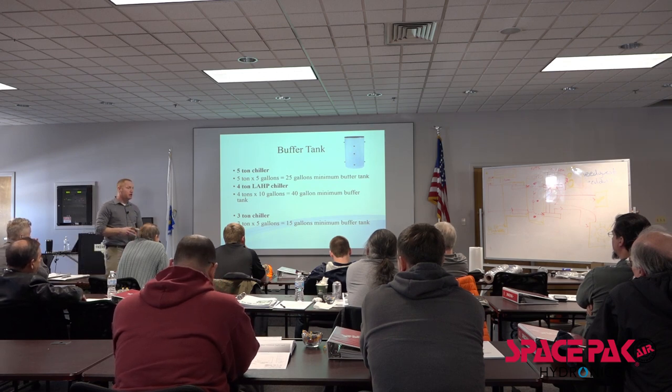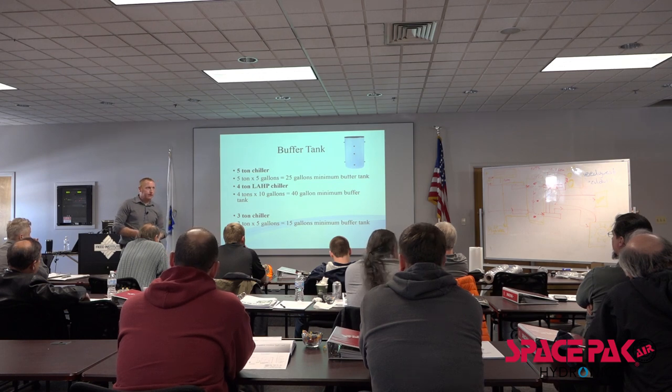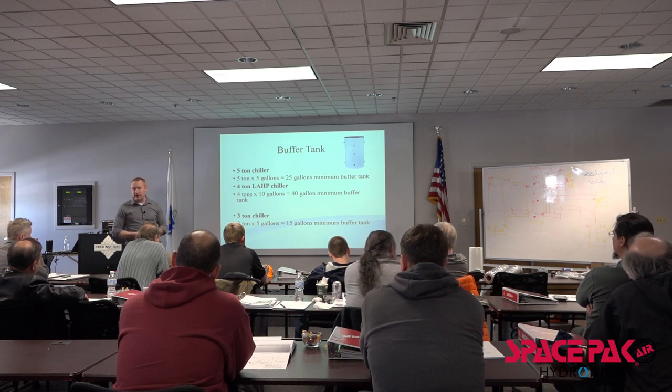We want, on our LAHP unit, a minimum of 40 gallons. Is it a detriment to have more? Nope, only if it takes up too much room in the basement. You know, I spoke with a gentleman who had 900 gallons in his basement, okay? If you can put an 80 in instead of a 40, it's just going to be that much longer.